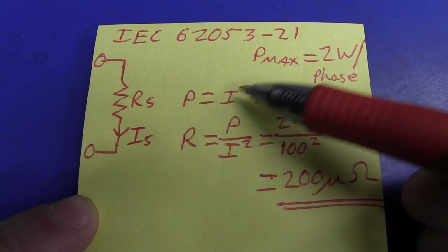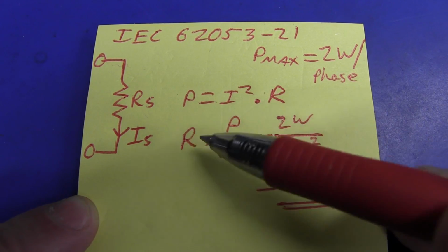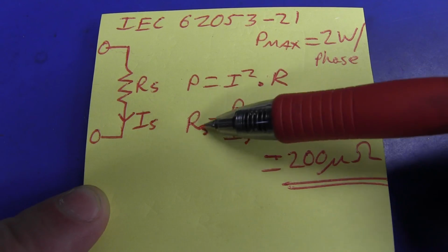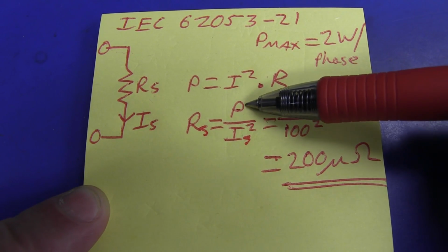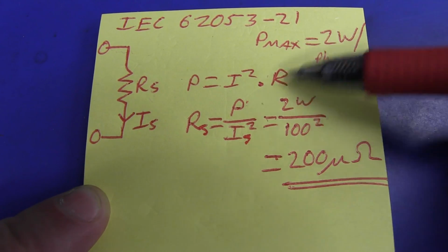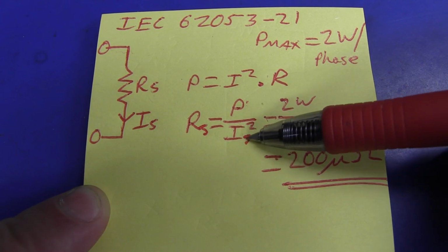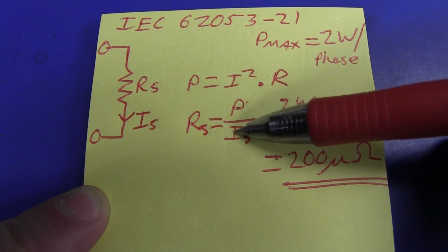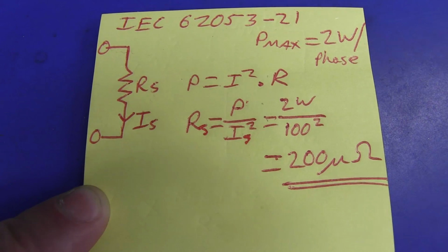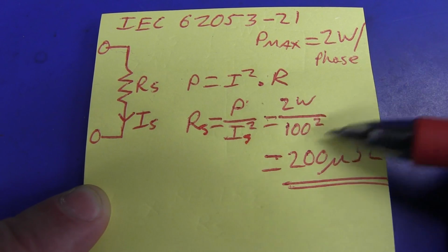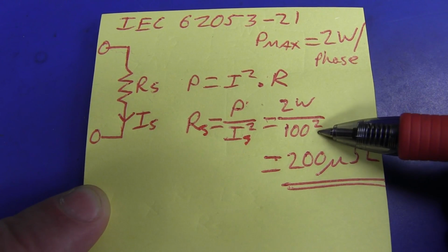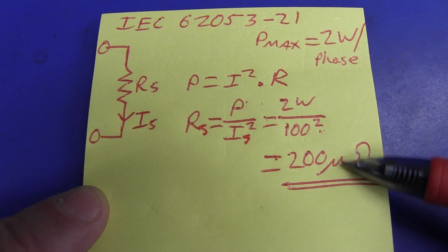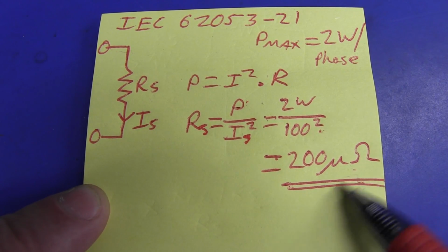So let's take 100 amps, and as you know, P equals I squared R. So rearranging that for our resistance, RS is going to be equal to the power, our maximum power in this case 2 watts, divided by IS squared, so that's 100 amps maximum capability - or if you design this meter to be 50 amps you can redo the calculation, but let's use 100. It's going to be in the order of, so 2 watts on 100 amps squared gives us a value of that resistor of 200 microohms.